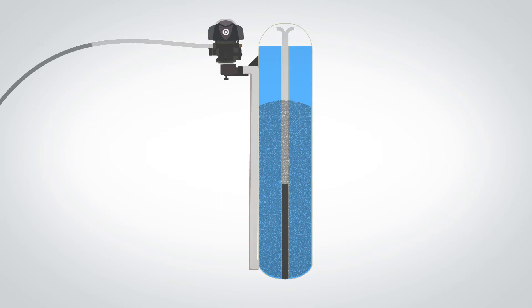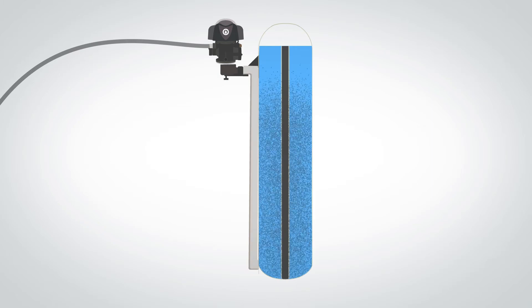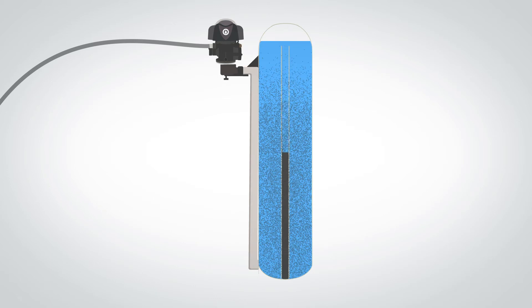It then enters a backwash step, where the control valve directs the flow of water up through the media bed from the bottom of the tank, lifting the bed and flushing any impurities down the riser tube and out the drain line. The backwash step also helps to reorient the media to eliminate any channels that may have begun to form.